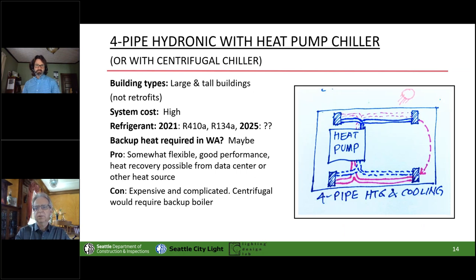Now, four pipe not only lets you be heating one side and cooling the other, but you see where the dash line on the right side is, you can then take some of that heat that you're removing from one side and use it as useful heat for another, where you've got variable loads, which really starts to make this shine as far as overall efficiency. And this is where I get really jazzed about central plants, where we start getting to share heat between the cooling and the heating, instead of having to make that heat with a boiler, although you're not allowed to use boilers some places now, or a heat pump chiller. It really ups the efficiency. It's exciting times, particularly in the right building occupancies, where you have something you always need to cool, something you always need to heat. It's a real win.